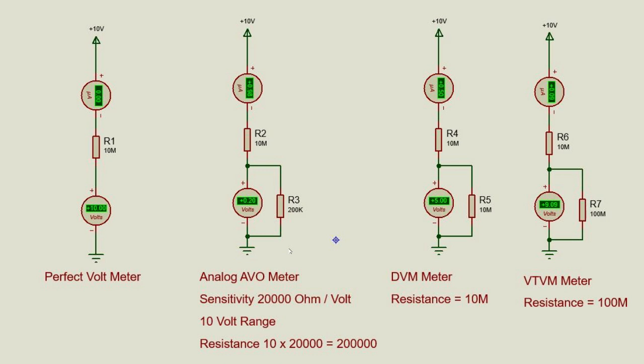Using Ohm's law, if we take our 0.98 microamps and multiply that by 10 megohms, that gives us a voltage reading of 9.8 volts, which is being dropped across the 10 megohm resistor. That means there's only 0.2 of a volt left for our voltmeter to indicate, because the voltage has been pulled down from 10 to just 0.2 of a volt.